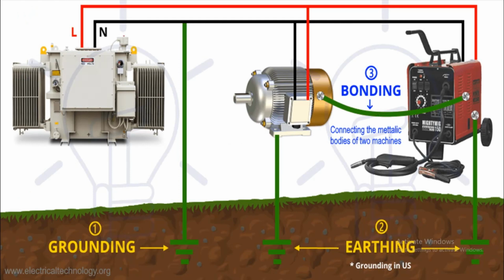So here is one example of a diagram of grounding and earthing. Earthing is also called grounding in the US, as you can see here in the two. Okay, so the grounding is connected to the neutral cable of the system and driven into the ground. And here on the right side as well, directly from the equipment or the machines, the earthing is connected to the ground. And we also have what is called bonding.